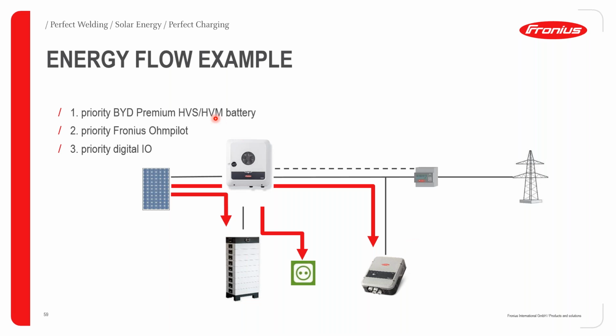So we can see that with the Gen 24 Plus, we are able to prioritize which are our important, critical energy areas. In this kind of setup, we have given priority 1 to the battery system. Of course, the load is always priority number 1, but in terms of setting up how you want to utilize all the excess energy, we can say our priority number 1 would be making sure that the battery system is completely charged. Then if we still do have excess energy and we have integrated a Fronius Ohmpilot, then priority number 2 would be feeding the Ohmpilot with the excess energy to generate hot water.